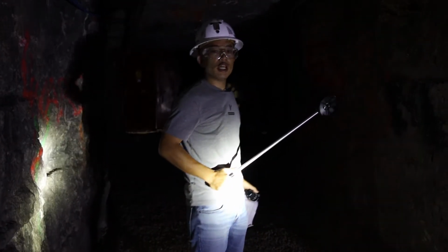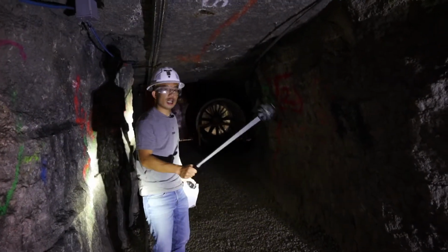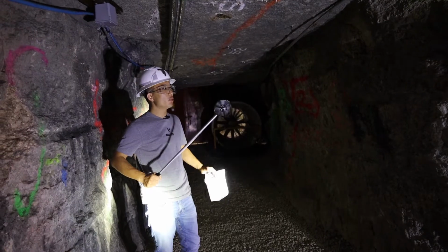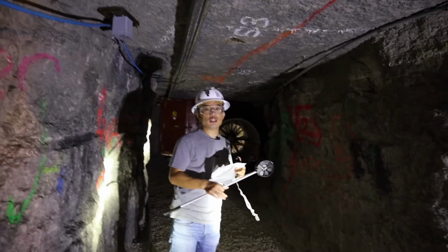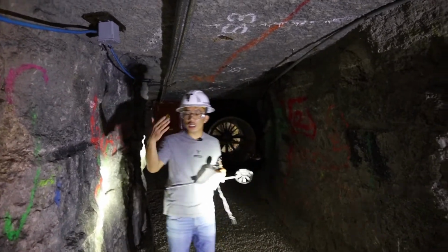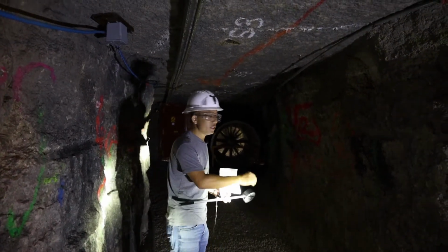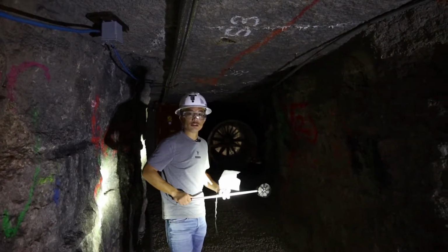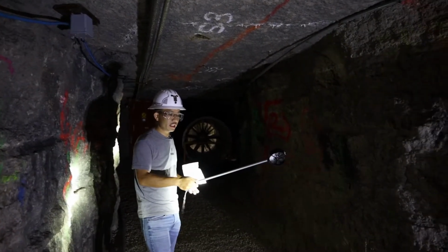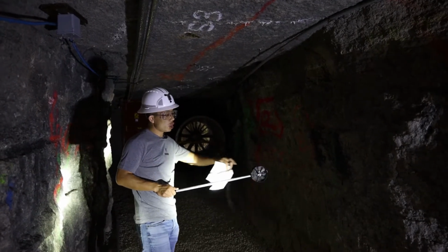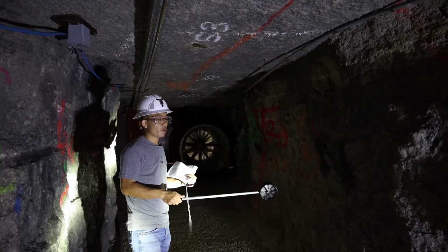The survey is done by moving the anemometer up and down, and covering the entire cross-sectional area of this airway, and then the velocity we calculate is going to be the average velocity over the entire cross-sectional area. Because the operator, me, has to stand in this airway, that will cause some interference to the airflow. That's why we need to use this extension rod, to make sure this anemometer is at least 1.2 meters away from the operator.